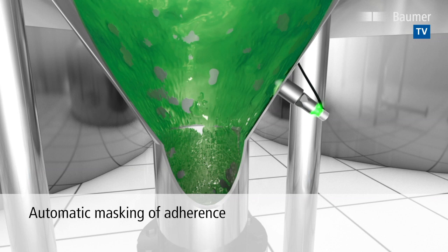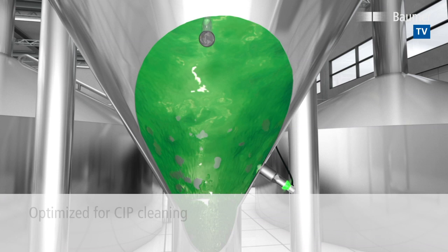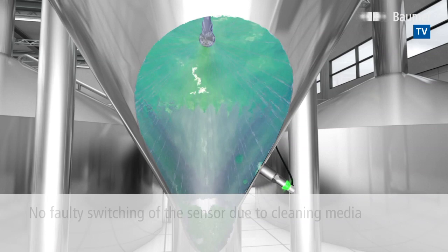As the Clever Level PL20 detects any adherence automatically, it automatically masks even accumulating adherence, thus increasing process safety. During cleaning processes such as CIP cleaning, sensors can become confused and switch incorrectly, since they cannot differentiate between the process media and the cleaning media. The Clever Level PL20 masters this challenge by ignoring cleaning media such as caustic soda solution and acids during the cleaning process.